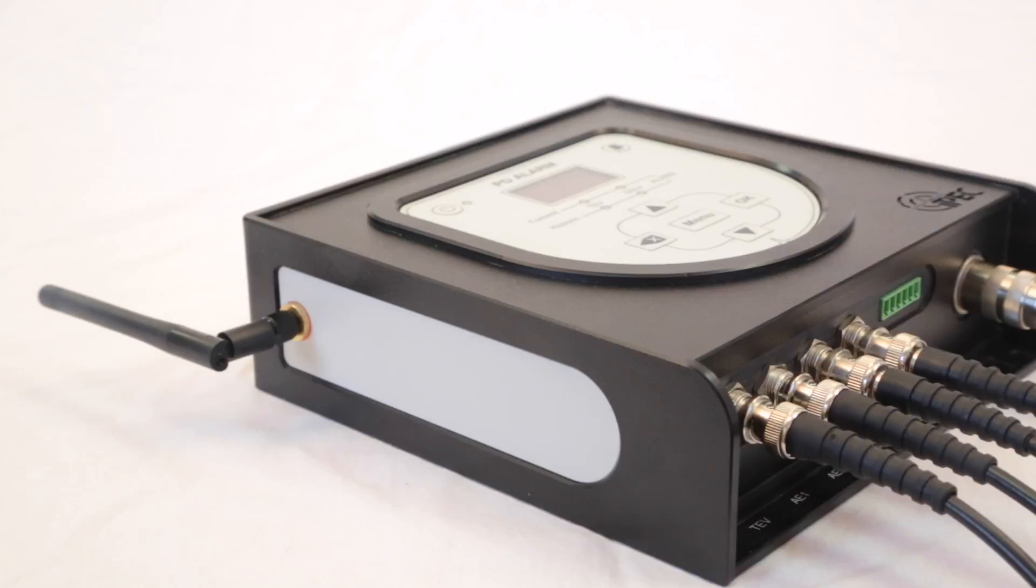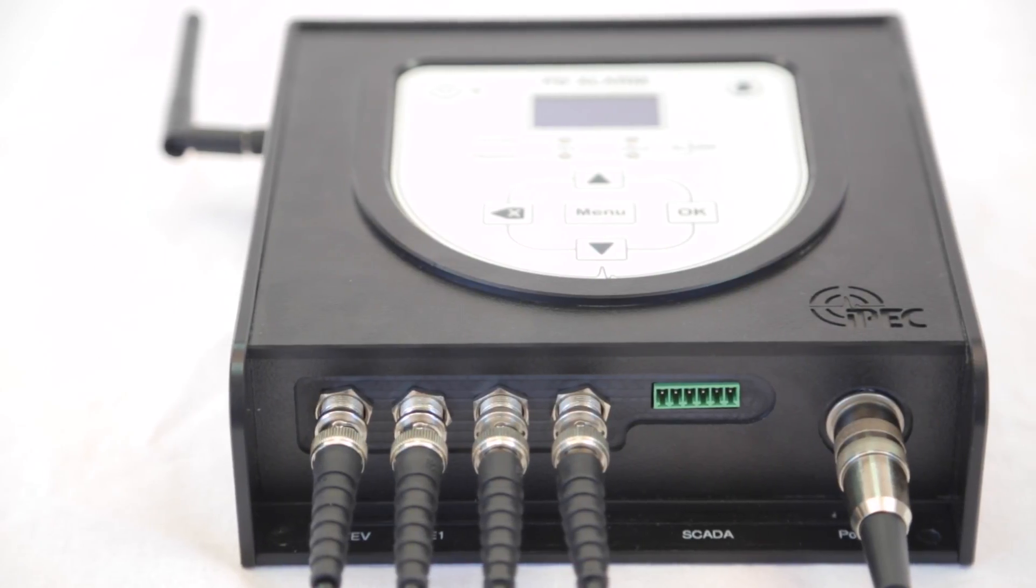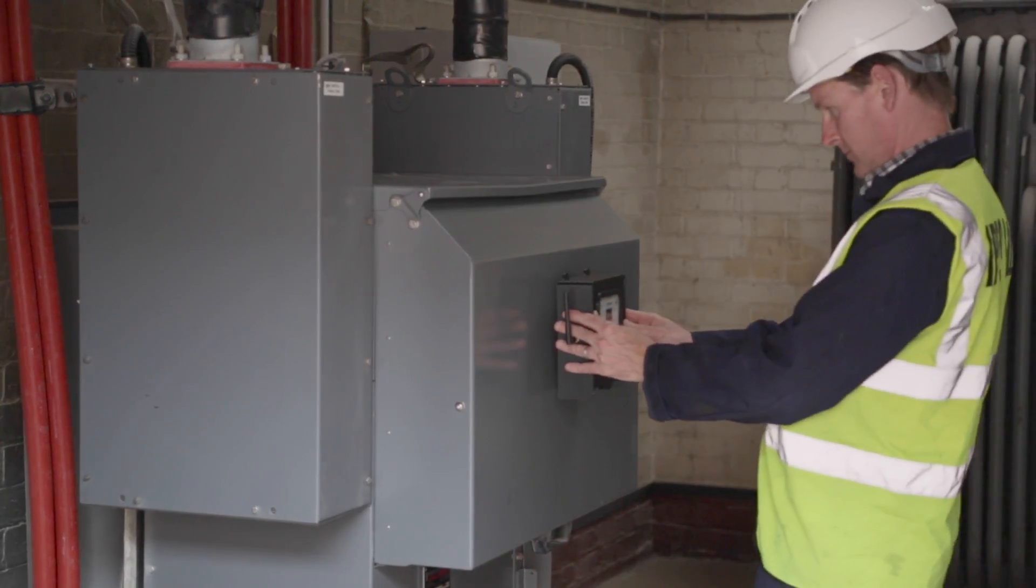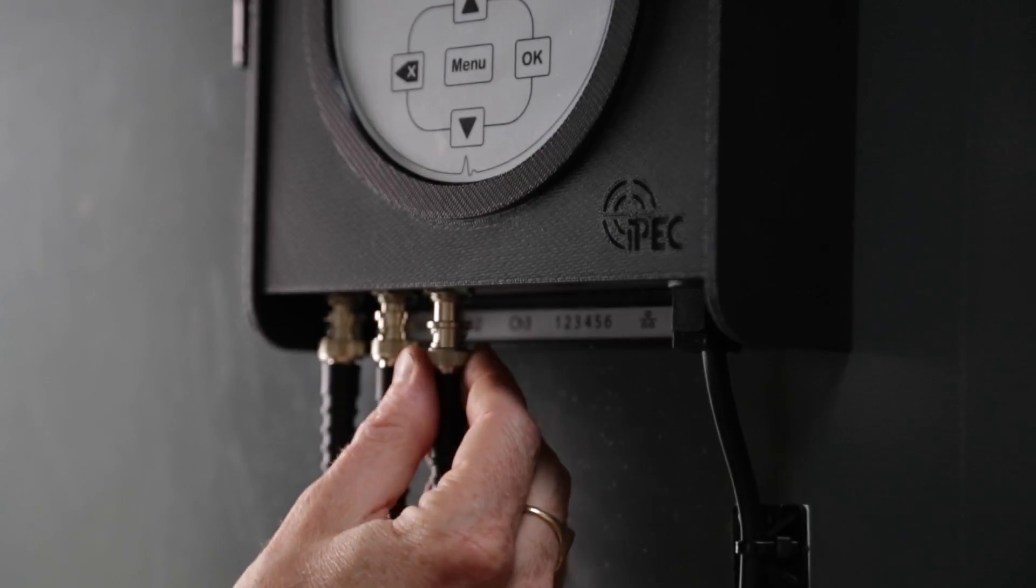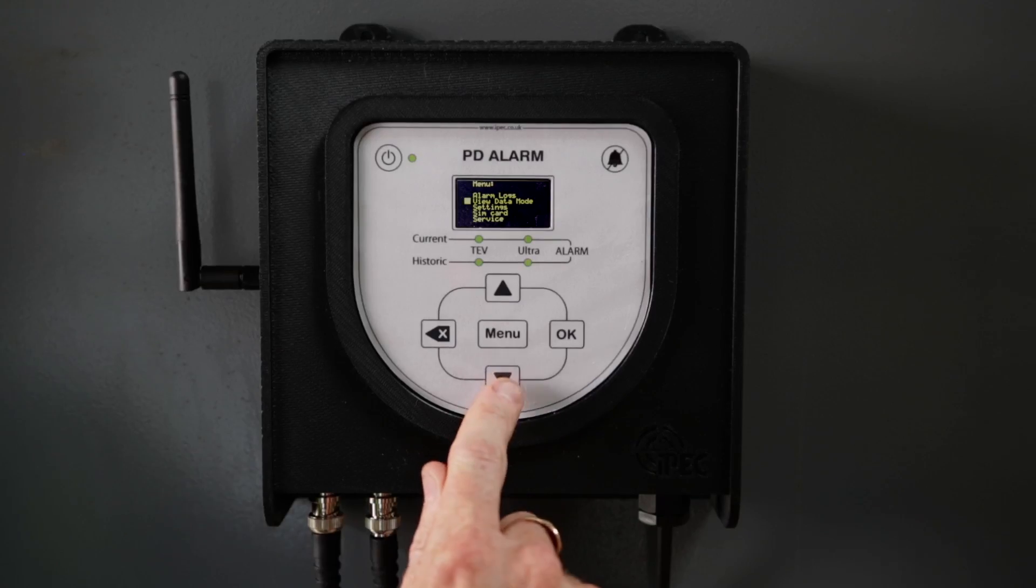The PD alarm is a brand new partial discharge monitor from IPEC. This small asset mounted instrument is used to indicate the presence of partial discharge in high voltage switchgear, ring main units, and transformers magnetically coupled to the switchgear. The PD alarm can be installed and set up in less than an hour without any high voltage outage required.